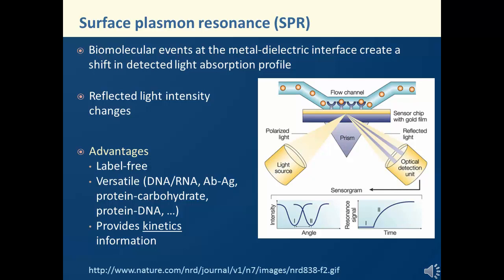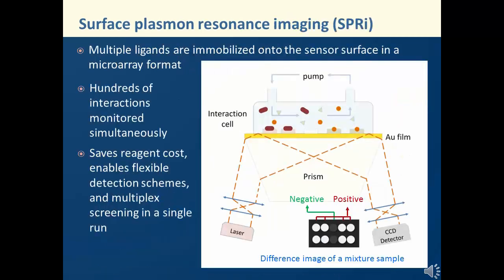SPRI can also provide kinetics data that can be directly used in characterizing a particular biochemical reaction. Traditionally, SPRI has only one to four fluid channels for analysis of a very limited number of samples at a time. The SPRI imaging technology takes SPRI analysis a step further. It allows the entire sensor surface to be visualized through a video CCD camera so that multiple ligands can be immobilized onto the sensor surface in a microarray format, and hundreds of interactions can be monitored at the same time. This can reduce reagent use significantly and shorten overall analysis time by allowing multiplex screening in a single run.